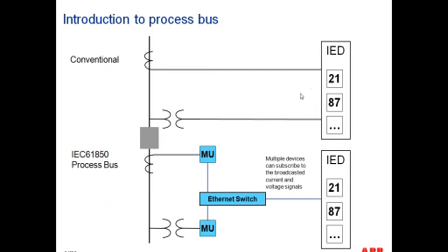So if we want to take a look at a visual of a sample architecture, what we have is essentially a relay in our control house, which is host to several protection functions. In the case of, let's say, line protection relays, we may have an impedance element and a line differential element, for example. And today, our voltage signals will be hardwired via copper from your VT onto the relay, and the same would be accomplished with our CT, our current transformer. There will be copper wire from our current transformer onto the relay. And then based on those currents and voltages that have been stepped down to secondary quantities, the relay essentially samples those signals, and based on that, it runs its protection algorithms. And that is actually the picture that we have here on top of a conventional installation.